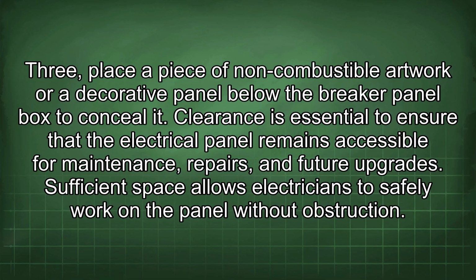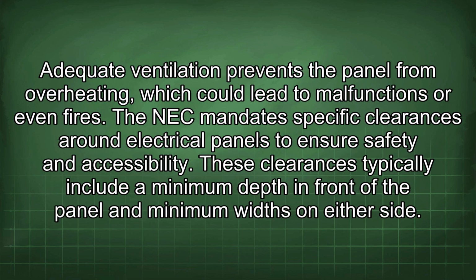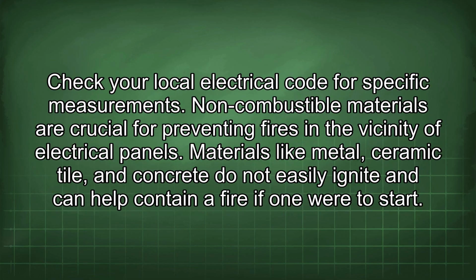Clearance is essential to ensure that the electrical panel remains accessible for maintenance, repairs, and future upgrades. Sufficient space allows electricians to safely work on the panel without obstruction. Adequate ventilation prevents the panel from overheating, which could lead to malfunctions or even fires. The NEC mandates specific clearances around electrical panels to ensure safety and accessibility. These clearances typically include a minimum depth in front of the panel and minimum widths on either side. Check your local electrical code for specific measurements.